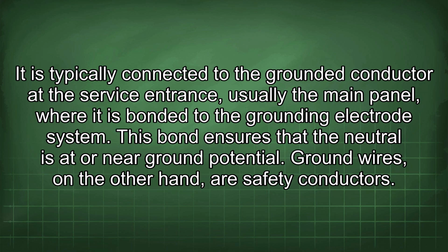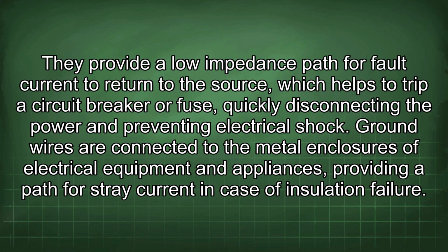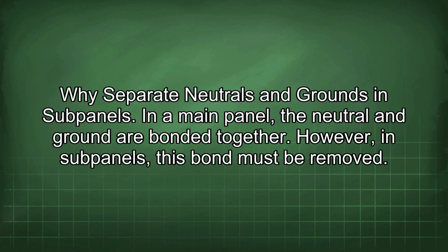Ground wires, on the other hand, are safety conductors. They provide a low impedance path for fault current to return to the source, which helps to trip a circuit breaker or fuse, quickly disconnecting the power and preventing electrical shock. Ground wires are connected to the metal enclosures of electrical equipment and appliances, providing a path for stray current in case of insulation failure. Why separate neutrals and grounds in subpanels?